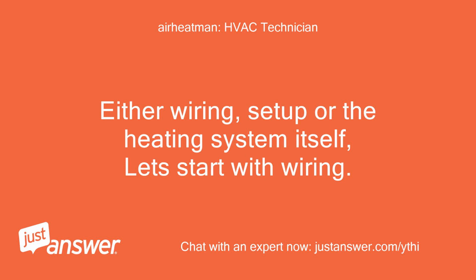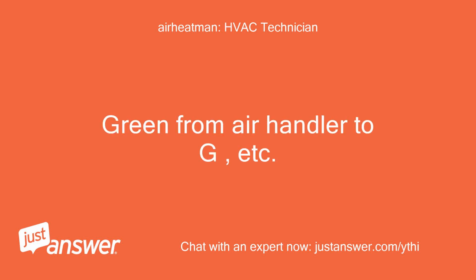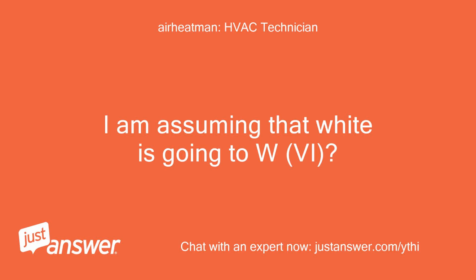Let's start with wiring. Tell me what wires are connected to what terminals on thermostat and an air handler. Example, red from air handler to R with jumper to RC. Green from air handler to G, etc. Red to R with light blue jumper between R and RC, white to Vi, yellow to Y, green to G, blue to C. Remainder of the terminals vacant. I am assuming that white is going to W, Vi?